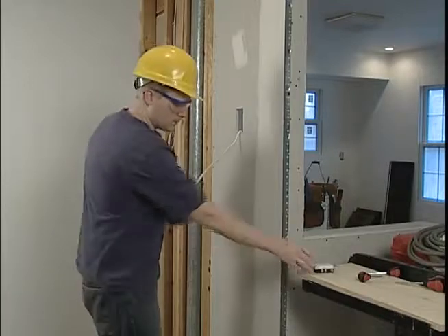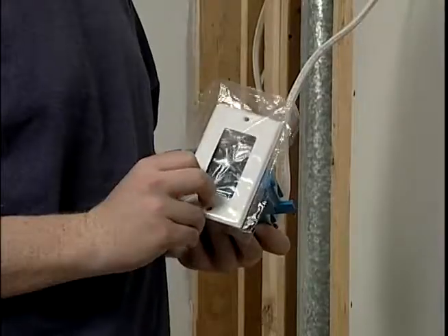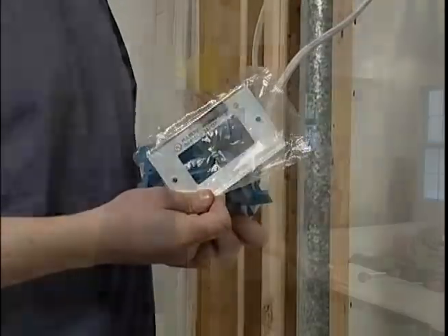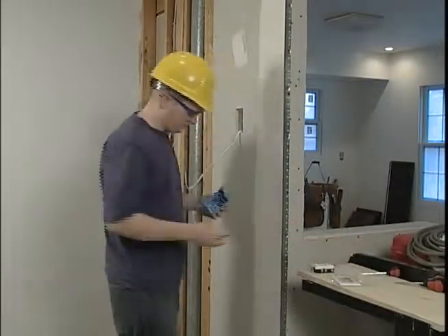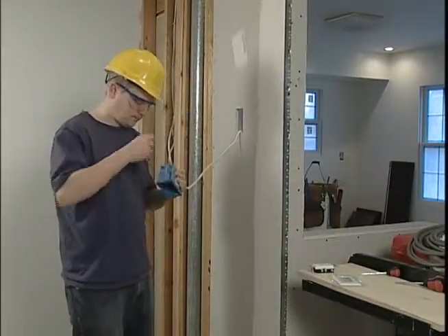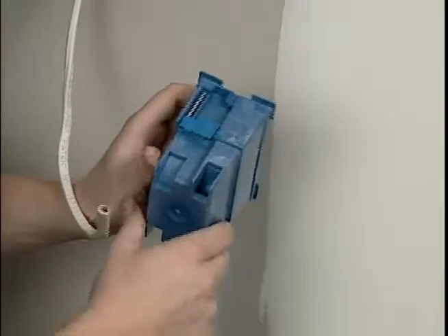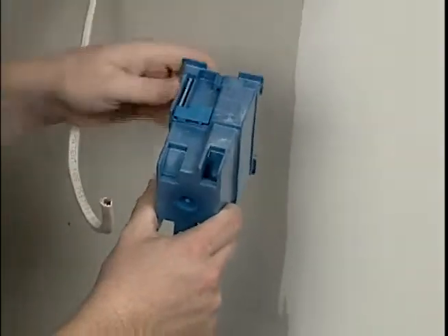In energized installations, each outlet box must have a cover, faceplate, or fixture canopy. Covers of outlet boxes that have holes for flexible cord pendants must include bushings or have smooth, well-rounded surfaces for the cords to rest on.